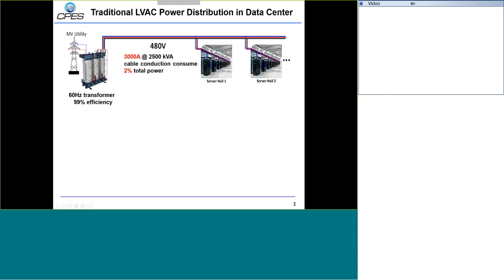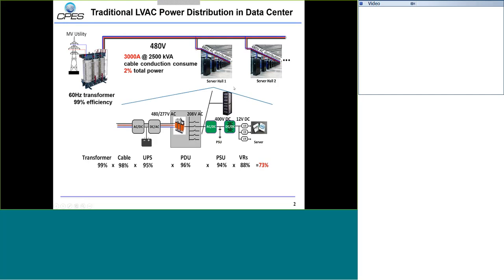In the future, this kind of conduction loss will become even higher. Also, within the server hall, because the input voltage is at least 480 volt AC, people normally use a UPS before delivering power to the server. You have an AC UPS and another transformer, and after this transformer the input becomes 200 volt AC. Then you go through the PFC AC-DC stage to get 400 volt DC, then step down further to reach the motherboard. There are so many power conversion stages that the total efficiency for this power conversion is just around 73%.